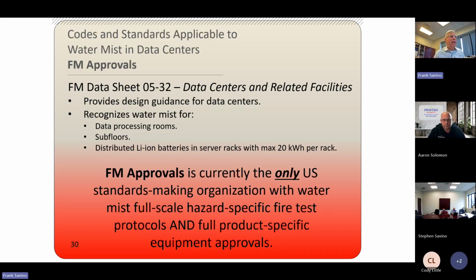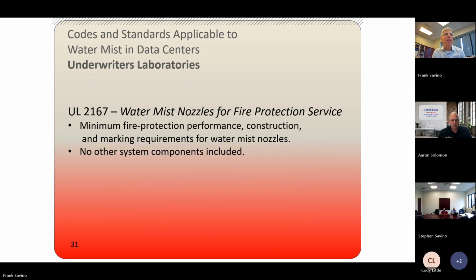And all the applicable codes and standards like the UCC and NFPA standards refer to equipment that is listed. Listed means tested by a nationally recognized laboratory, which Factory Mutual is, that is acceptable to the authority having jurisdiction. So really what I'm saying is Factory Mutual is it, okay, with regard to water mist systems. UL has a really minor role, almost insignificant. They do have listings, but they just have equipment approvals. Like they'll say, okay, this nozzle passes the UL test for corrosion or the drop test. It's almost not even worth paying much attention to. They have a very minor role in the approval making process.